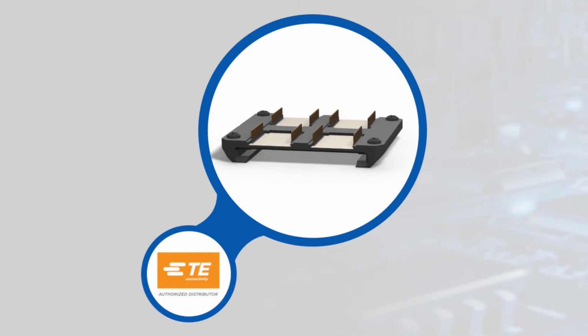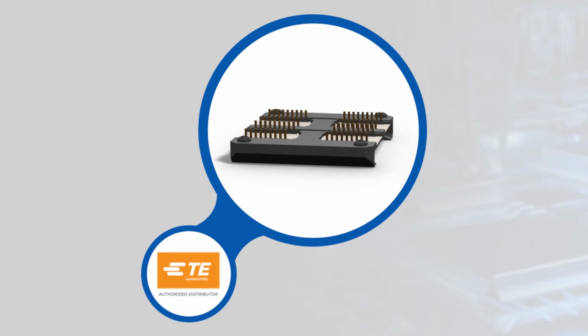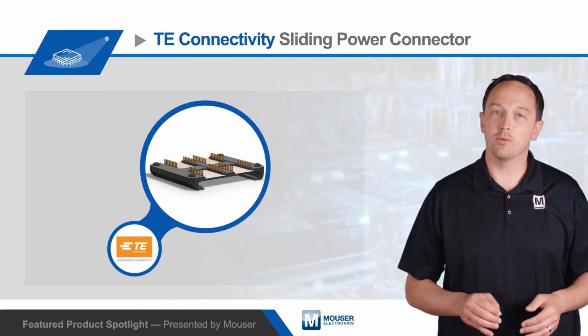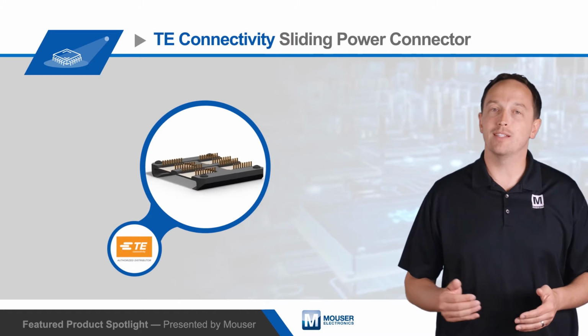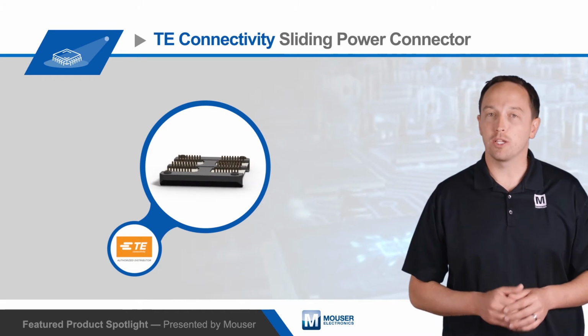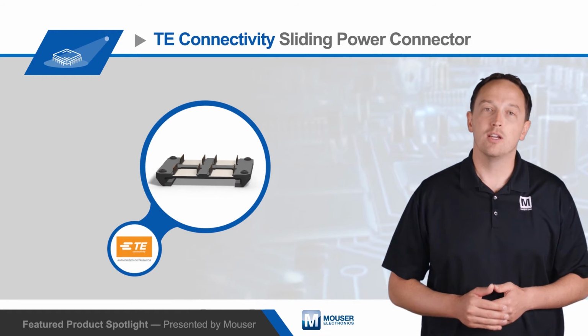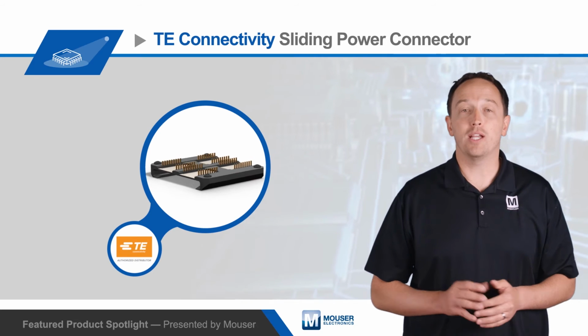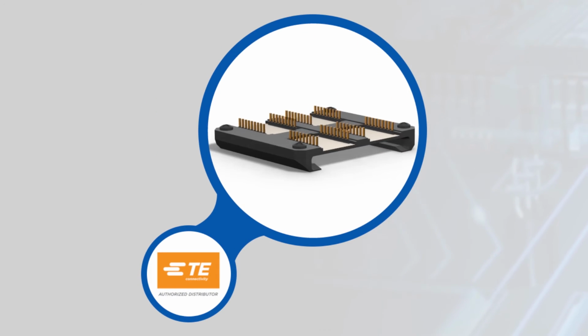It's constructed from spring finger copper alloy contacts with gold over nickel plating in a black thermoplastic housing, with compliant pin termination to the PCB. The connector mates to a baseboard rail that slides into and through the housing, with exposed traces on the baseboard contacting the spring fingers of the sliding power connector to power the application, with ideal applications including hard drives, power supplies, OCP cubbies, servers, and other high current devices.